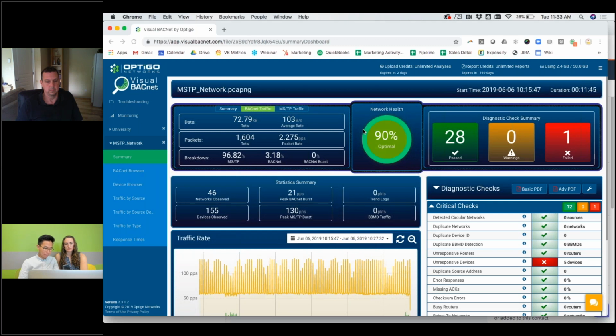You can request a confirmed COV. You can set it up differently. You could have a confirmed COV that's not receiving a reply, and that would be a bad thing. So this is an unconfirmed one, so it's saying, here's the data, don't respond. Don't confirm to me that you've received it. If it's really critical and you want to make sure the data is actually making it through, you could set up a confirmed COV that would double your traffic. Every time the data gets sent, it gets a response. So yeah, if you confirm it, it comes back. All right.